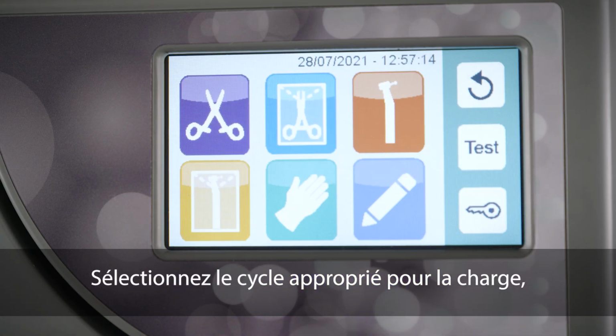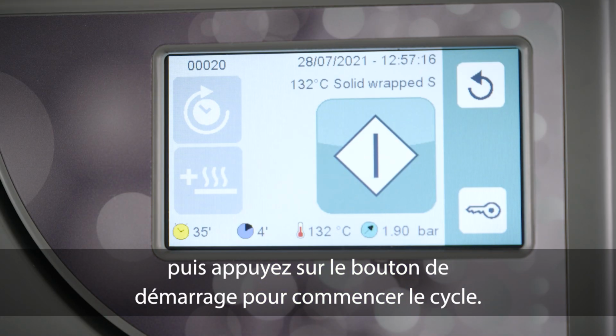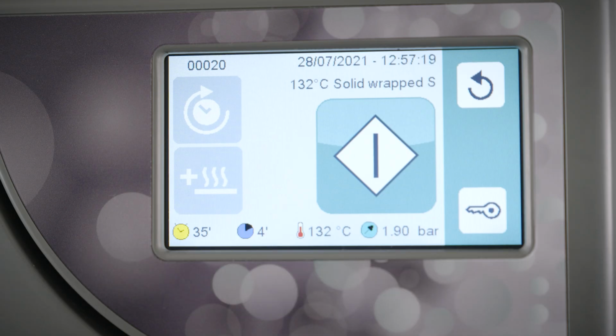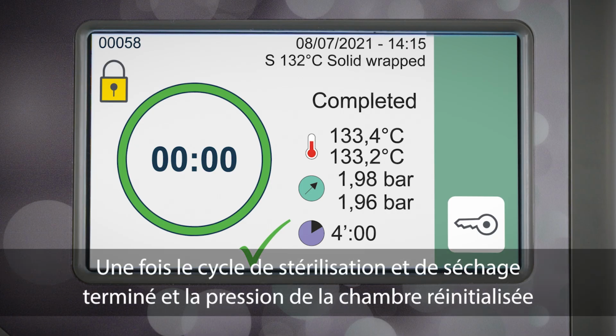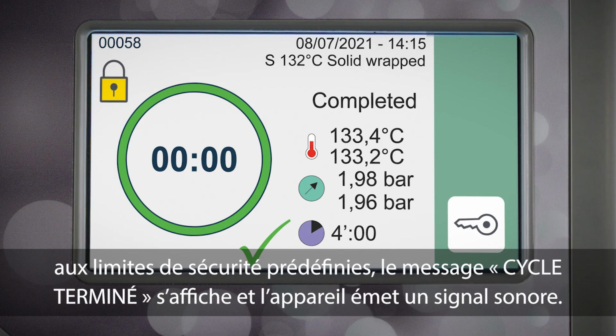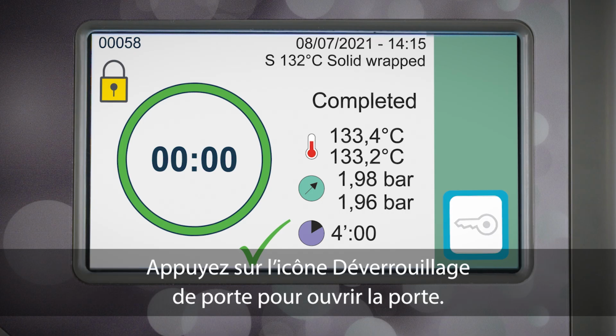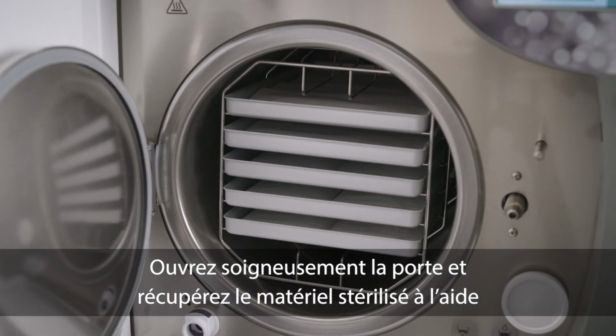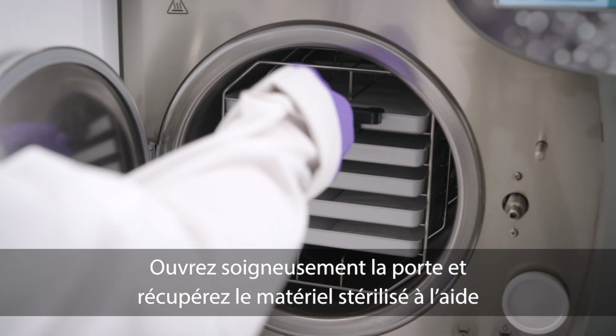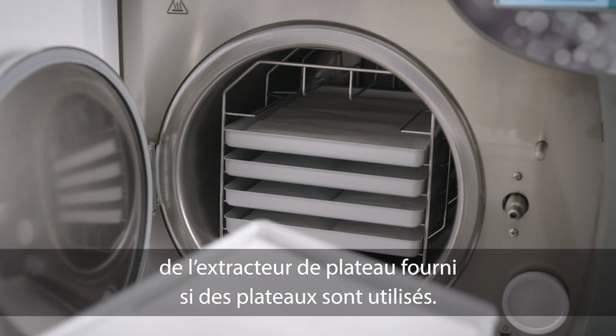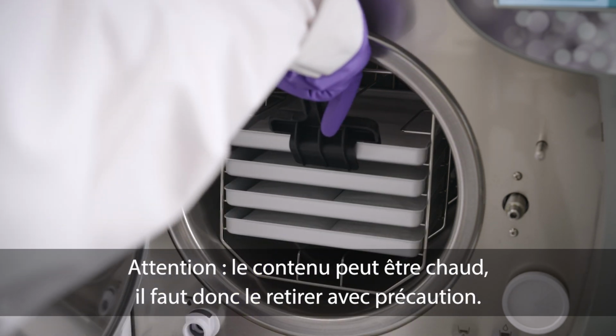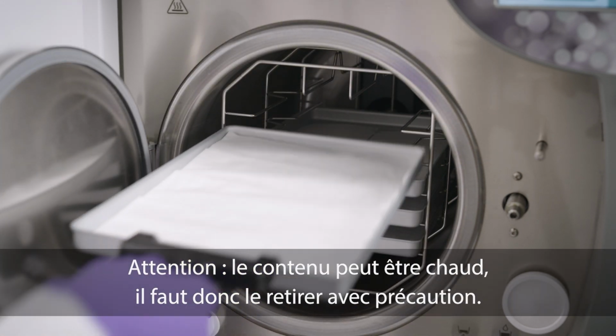Select the cycle appropriate for the load, and then press the Start button to begin the cycle. When the sterilization and drying cycle is complete, and the chamber pressure returns to the preset safety limits, the message "Cycle completed" is displayed and the unit will audibly beep. Press the Door Unlock icon to open the door. Carefully open the door and retrieve the sterilized material using the tray extractor provided if using trays. Caution: contents may be hot, so remove with care.